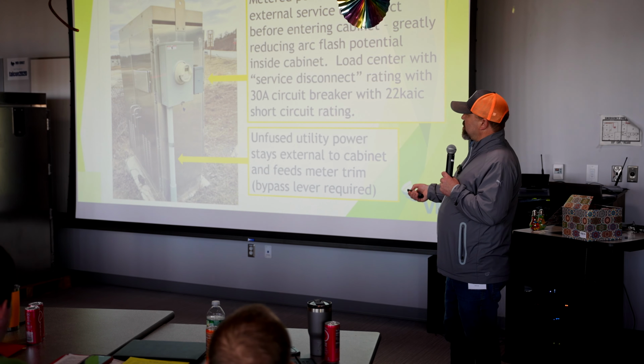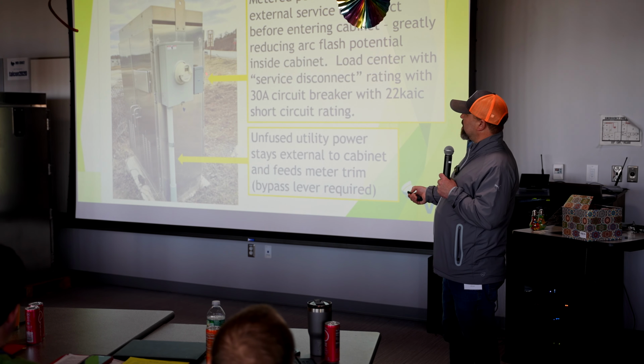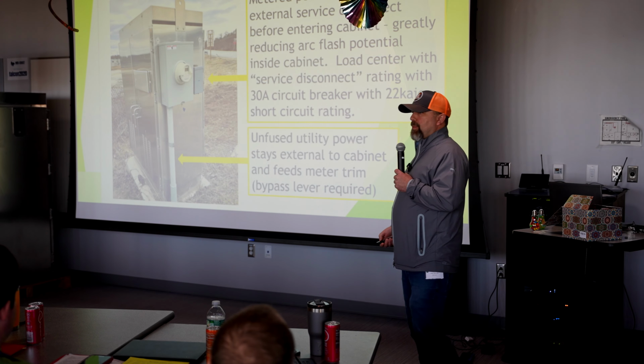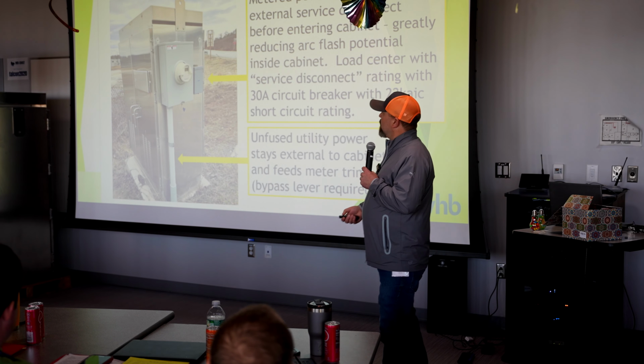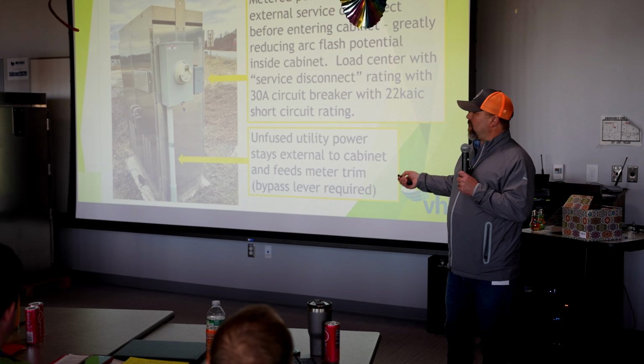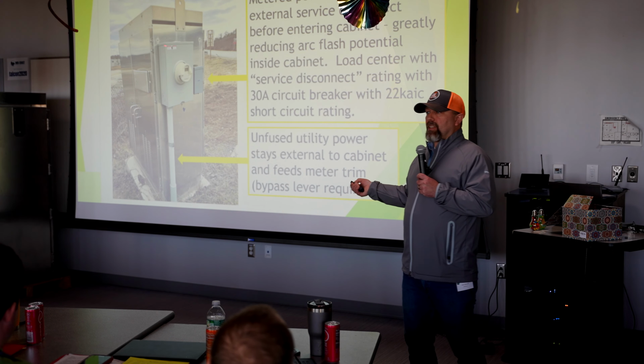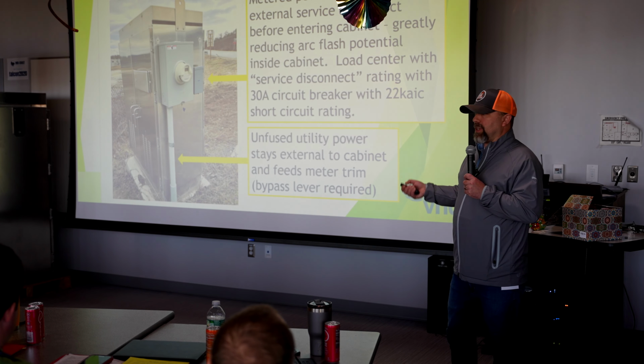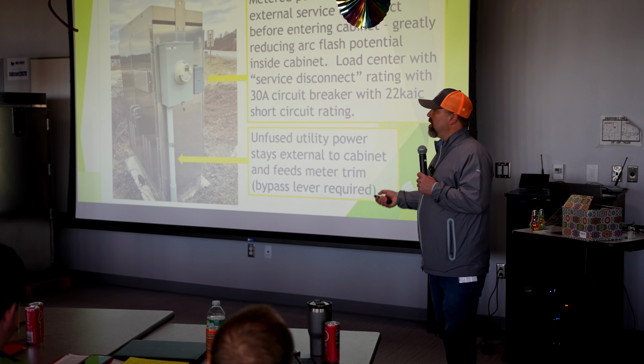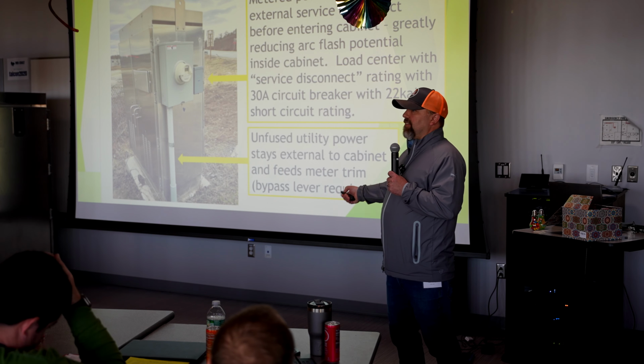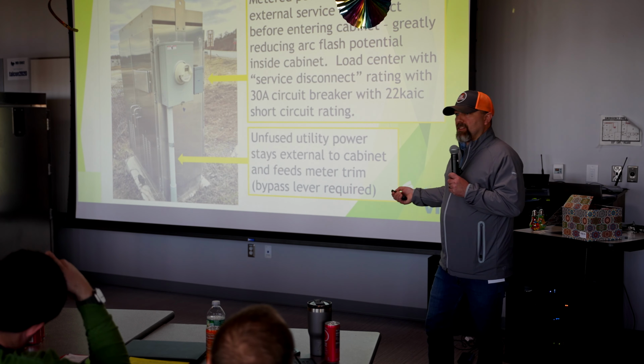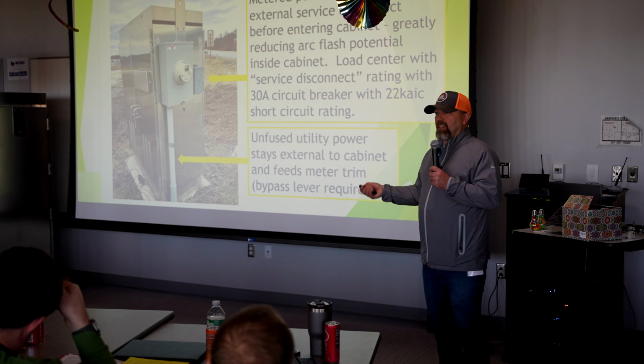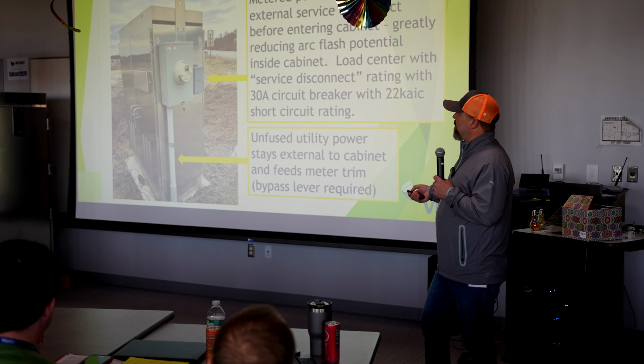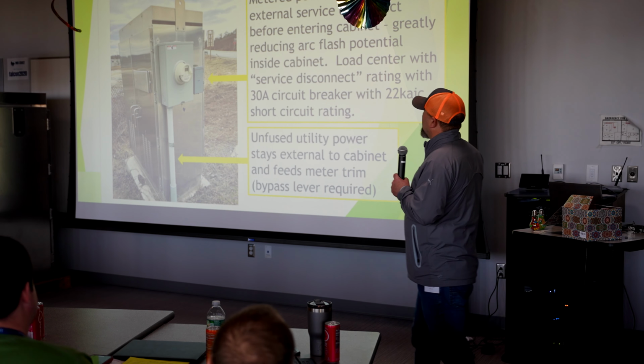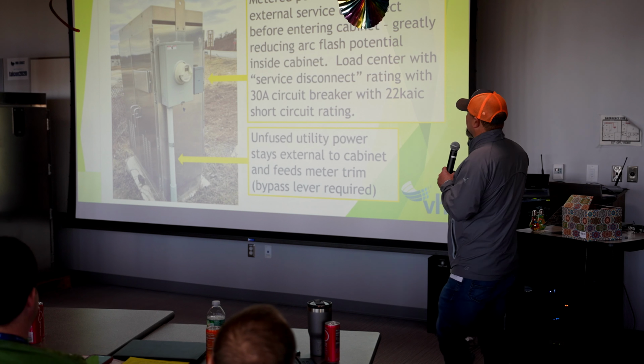What this also allows us by doing this is that you can now have an externally mounted service disconnect. What that does is greatly reduce your arc flash potential, because you now have an overcurrent device before anything even enters the cabinet. So the cabinet basically becomes a branch circuit in the electrical world. You're really minimizing that arc flash potential.